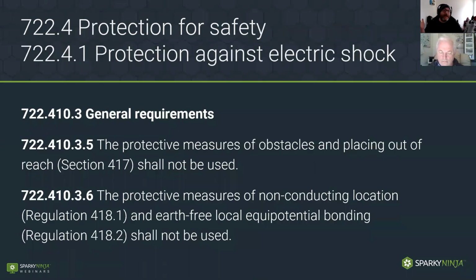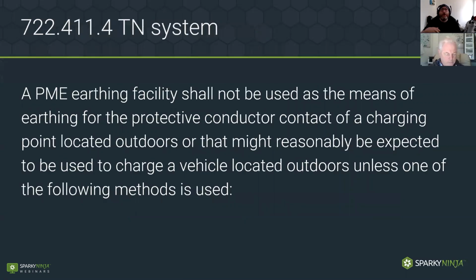So we enter into protection for safety, protection against electric shock. The first thing you can see is the common thing that you see in all of Part 7 special locations, where those protective measures, obstacles, placing out of reach, non-conducting location, all those, they're not acceptable. Yeah, that's the same for all special locations. Those are specialized protective measures, so they are not suitable.